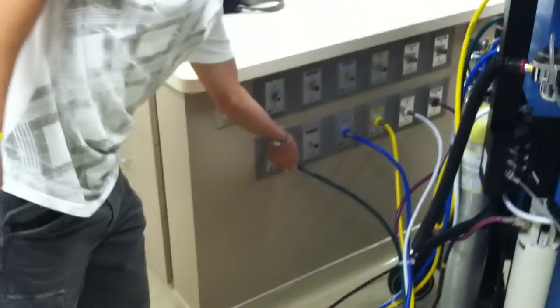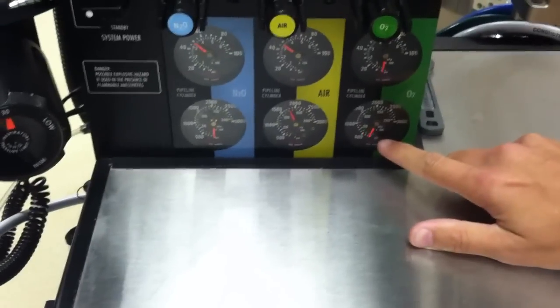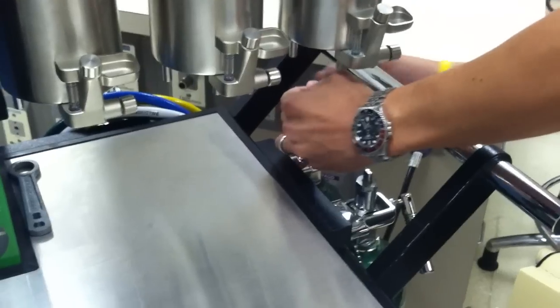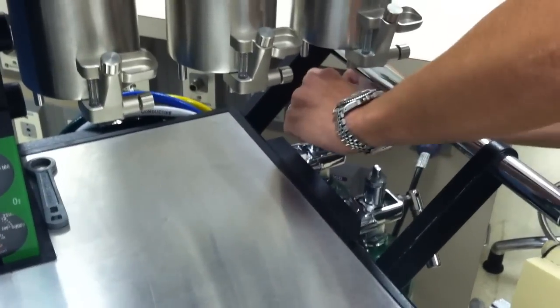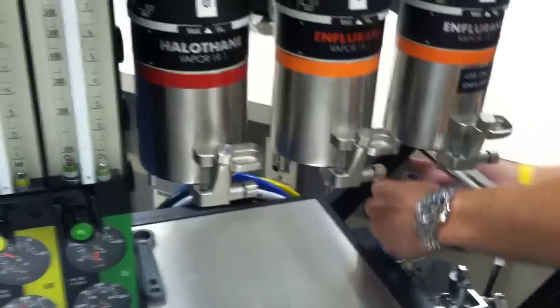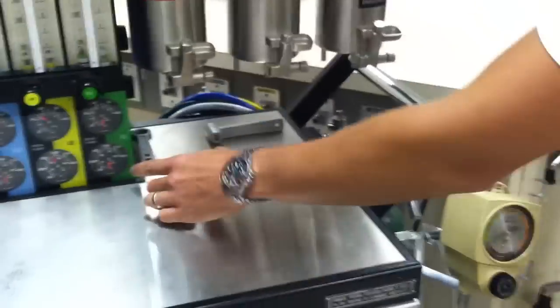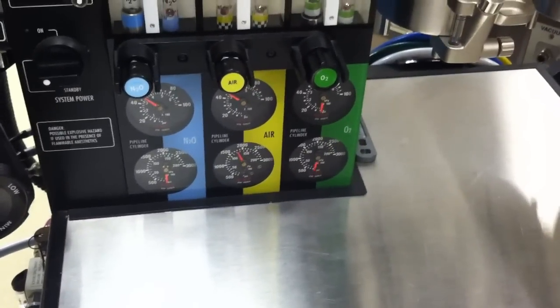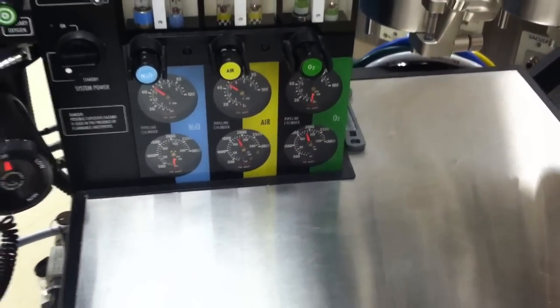So I'm going to disconnect, come around here, push my O2 flush, and you're going to see that go down. And then I'm going to open up my second cylinder, open it up, close it. Now this one didn't have any pressure in it, but if it had pressure you would see it go there. And I'm going to show you again to prove that. We're going to open this one. It goes to about 2,000 again.